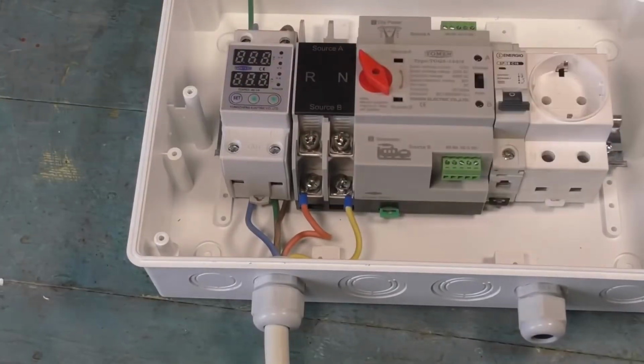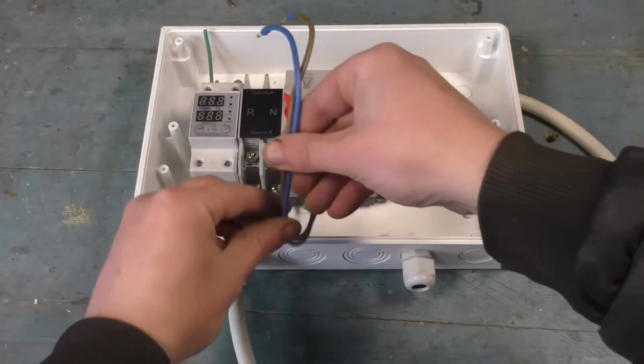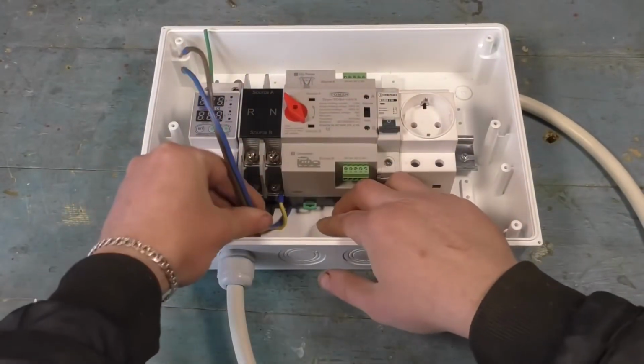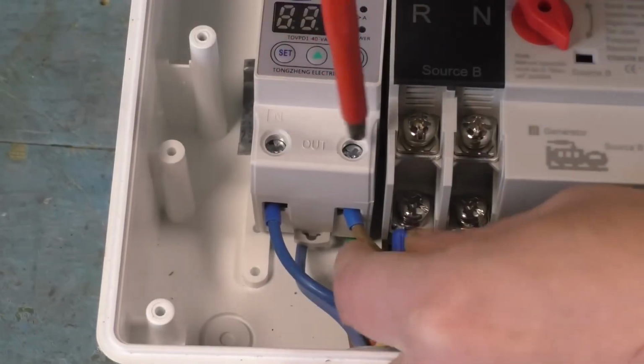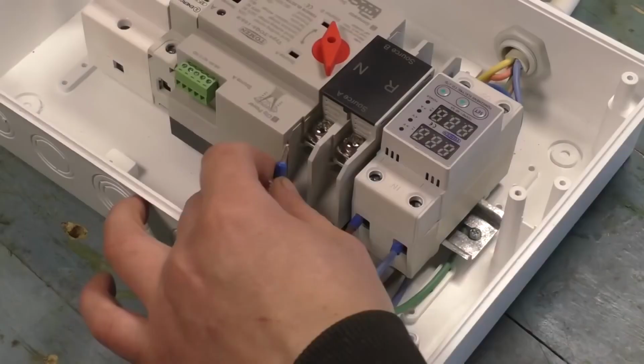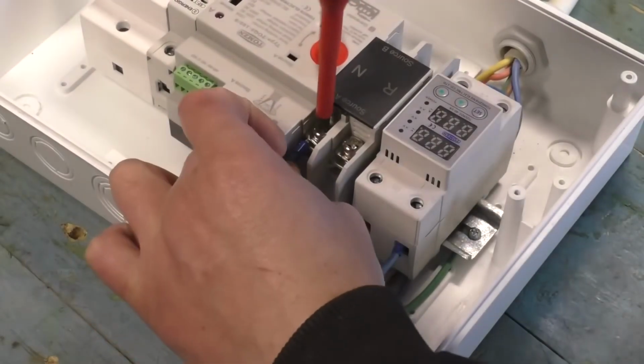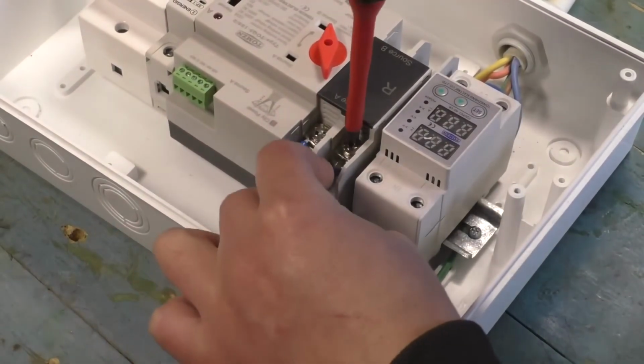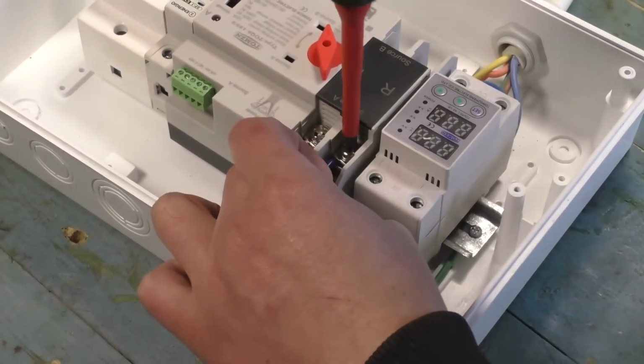For the Thomson ATS, we take 2 jumpers and place them under the first rail, then connect these jumpers to the output of the voltage relay. Blue is neutral, red is phase. Everything is labeled on the relay. The opposite ends of these jumpers are connected to the input. On the Thomson ATS, neutral is connected to terminal N and phase to R.